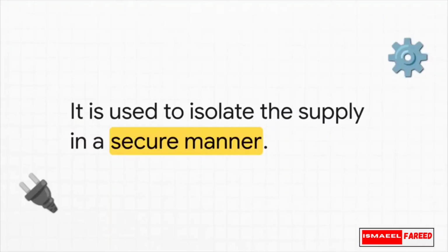So we have to talk about the exception to the rule here, stepping away from standard breakers completely to look at the isolator. Visually, an isolator might look exactly like the standard B, C, or D type breakers sitting right next to it on your panel. It's got a switch, it's in the exact same plastic housing, but functionally, it is a completely different tool. And mistaking it for a true circuit breaker is a really dangerous fundamental error.